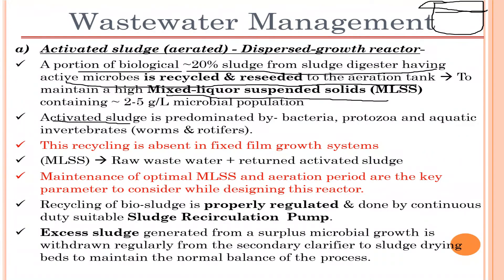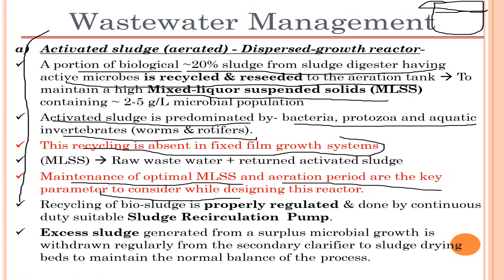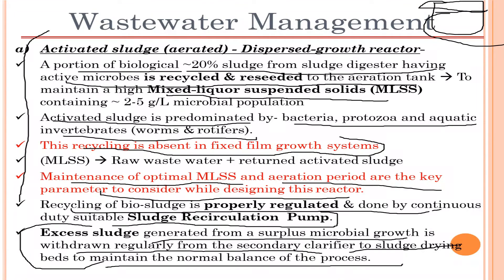The activated sludge is predominated by bacteria, protozoa, and aquatic invertebrates such as worms and rotifers. This recycling is absent in fixed film growth systems and is only present in dispersed growth systems. Maintenance of optimal MLSS (mixed liquor suspended solids) and aeration period are key parameters in designing the reactor. Recycling of bio-sludge is regulated by a continuous sludge recirculation pump. Excess sludge generated from surplus microbial growth is withdrawn regularly from the secondary clarifier to sludge drying beds to maintain normal process balance.